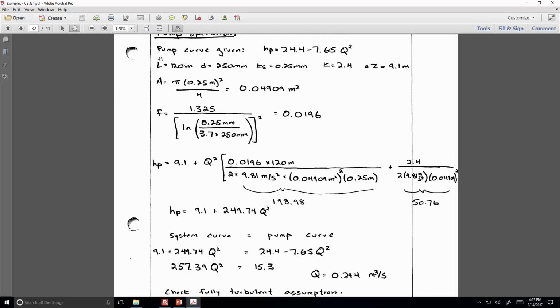So we are given a pump curve by the manufacturer of the pump, basically a description of that trade-off between flow rate and pump head that it can achieve. And then the system curve we assemble based on the physical characteristics of the system: the pipe's length, its diameter, the material of the pipe, which defines the relative roughness, the K values, which are those local losses like valves and bends and so on, and the delta Z, which is the elevation difference.